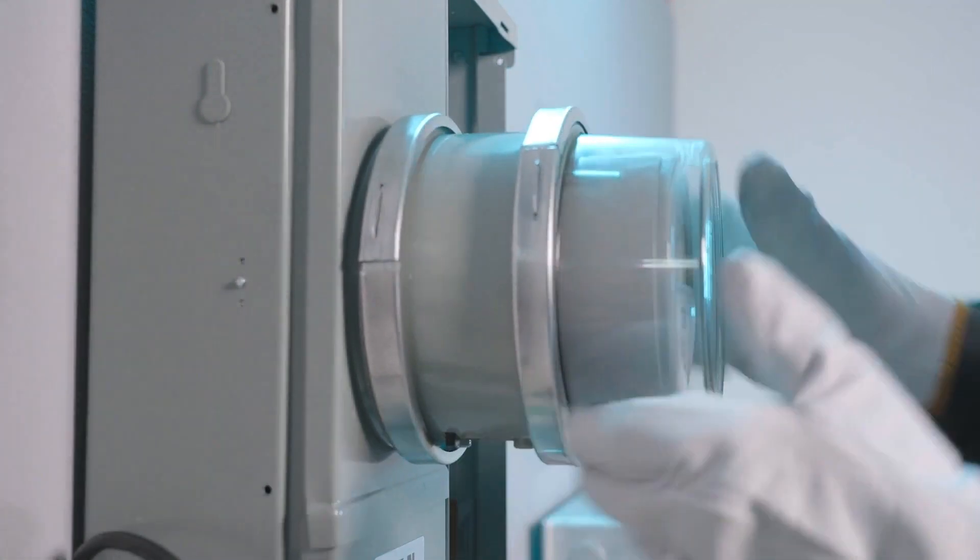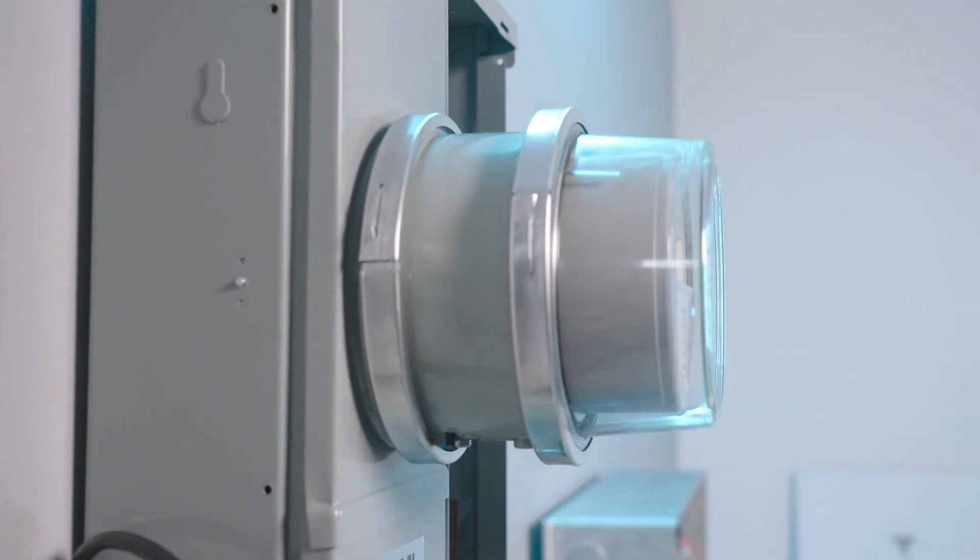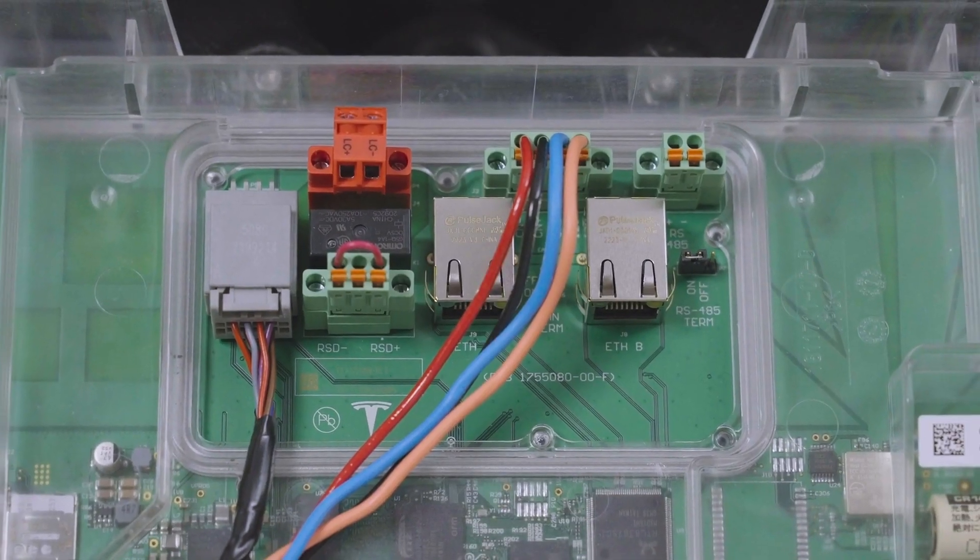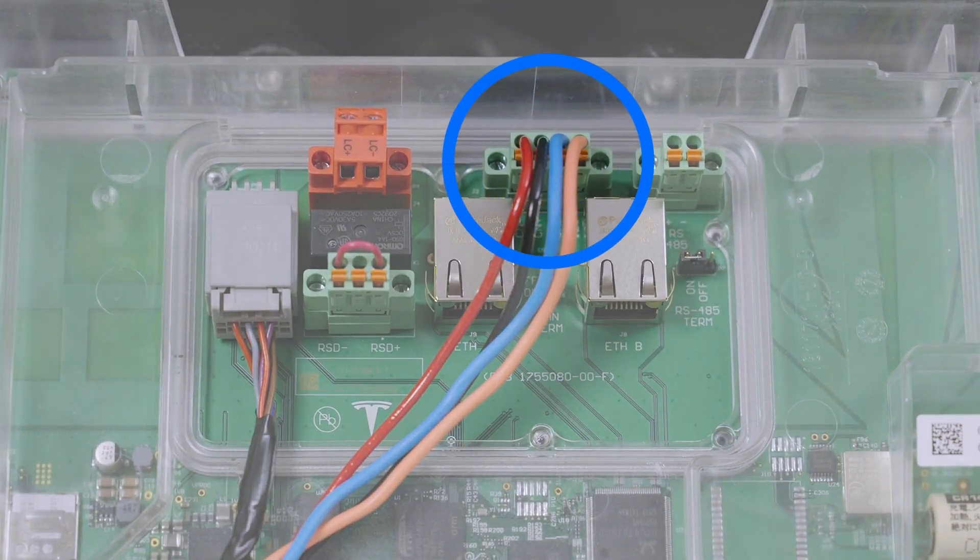Perform a pull test to ensure Backup Switch feels secure in the meter panel. If Backup Switch does not feel secure, verify that the sealing rings were installed in the correct orientation. Backup Switch is now installed and ready for wiring.